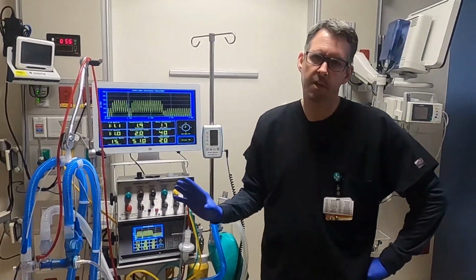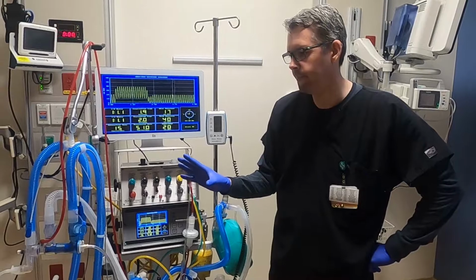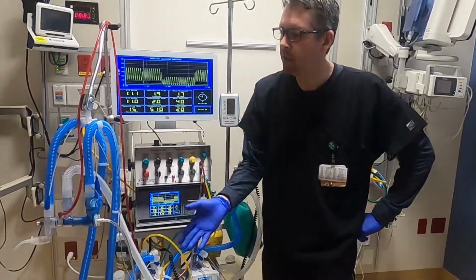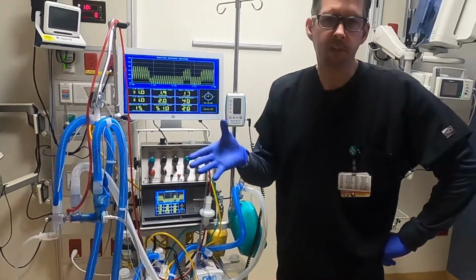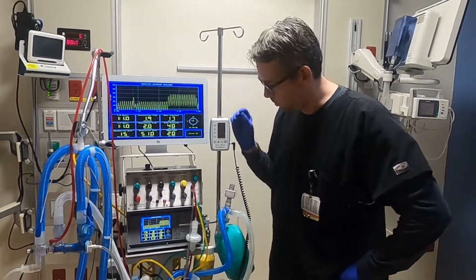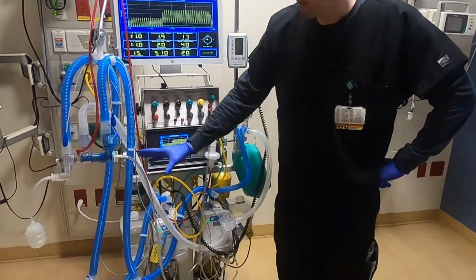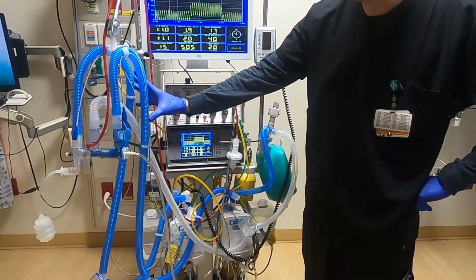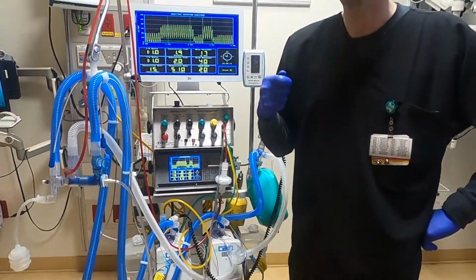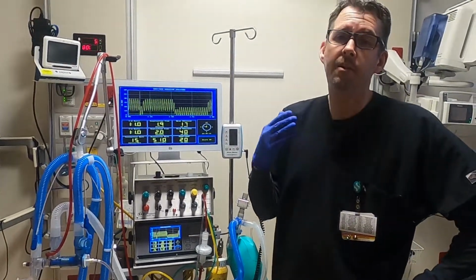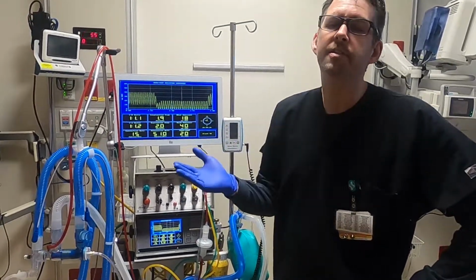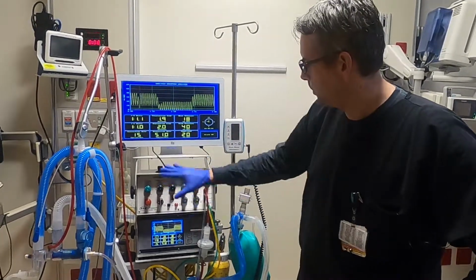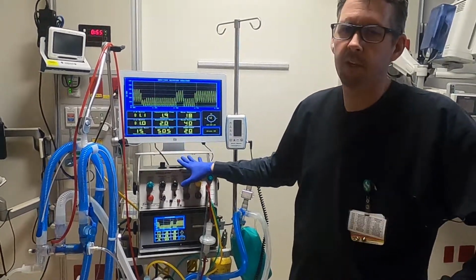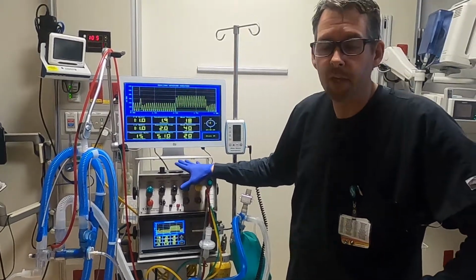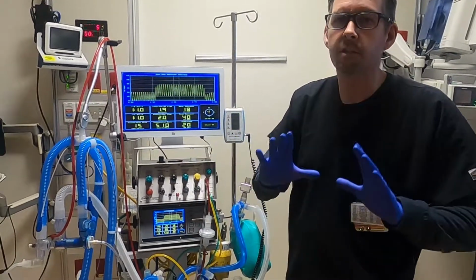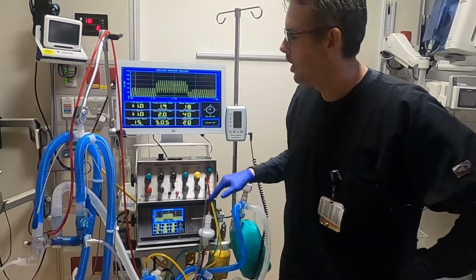One of the main considerations for this ventilator is that there's so much flow going through here, so much gas, that patients can become dry. So one of the really important things is making sure that your circuit is humidified and patients are suctioned frequently, and one of the ways you can tell is by the chest moving. This machine, we can set the pressures on it, but it's not telling us what the tidal volumes are. So the way we're going to be able to really see what's going on is to actually watch the patient's chest moving.